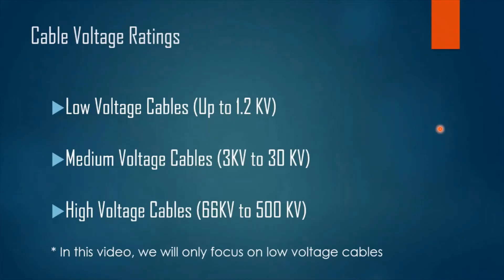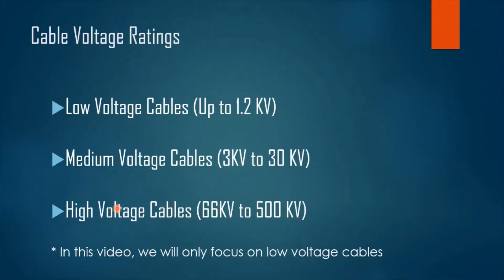Now let's know more about voltage ratings of a cable. We have three categories: the first is low voltage cables, which can withstand up to 1.2 kilovolts; the second is medium voltage cables, which can withstand 3 kilovolts to 30 kilovolts; and the third is high voltage cables, which can withstand 66 kilovolts to 500 kilovolts. For now, we will focus on the first category — low voltage cables.